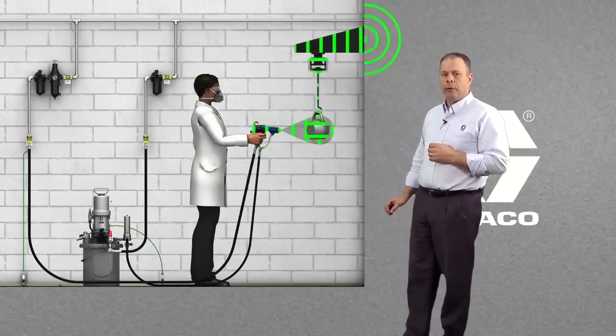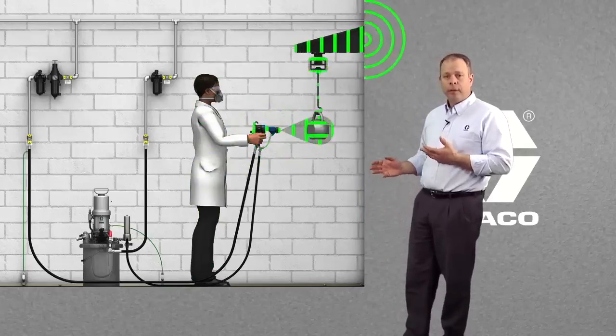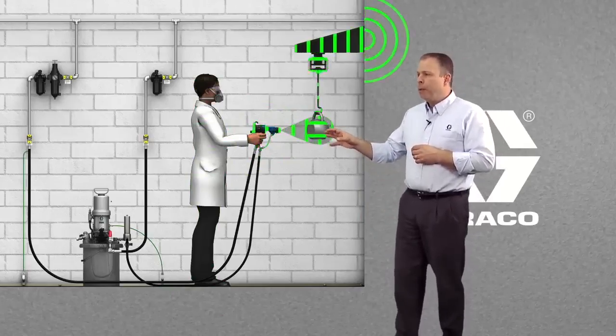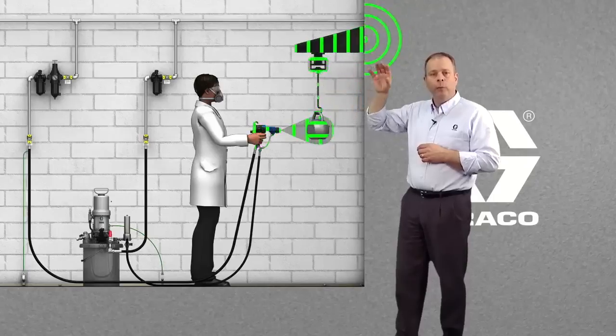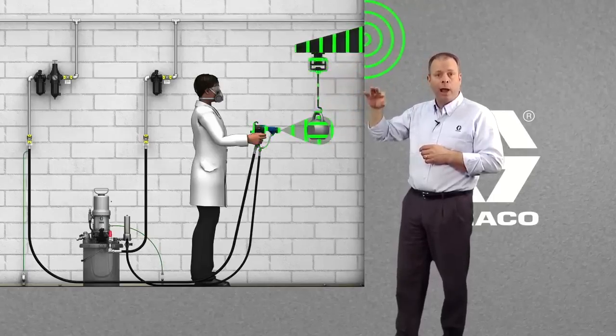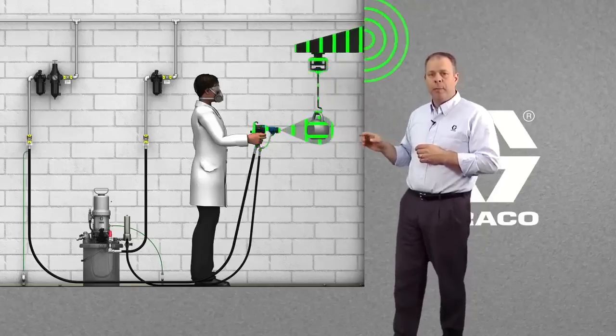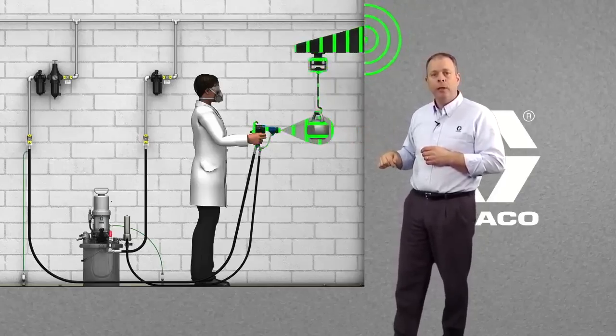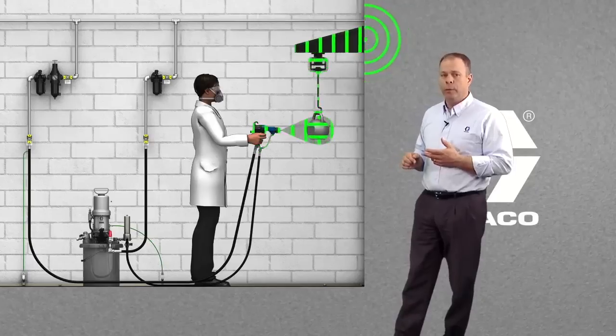We're going to talk about the grounding of the part itself. From my part through the conveyor, we want to make sure we have a true, good, true earth ground. And what that means is from a measurement from the part to earth ground should be no more than one megaohm resistance.